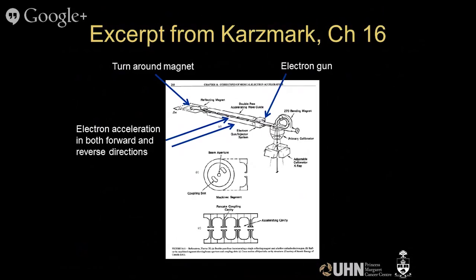So this is what you see over here. The way this worked, with the electron gun over here, the electrons are accelerated down the waveguide, they turn around, and the turnaround magnet could be placed at the right position so that the electrons could then be sent back towards the gun again, and then through a bending chamber, and then they could have up to twice the energy of the waveguide.